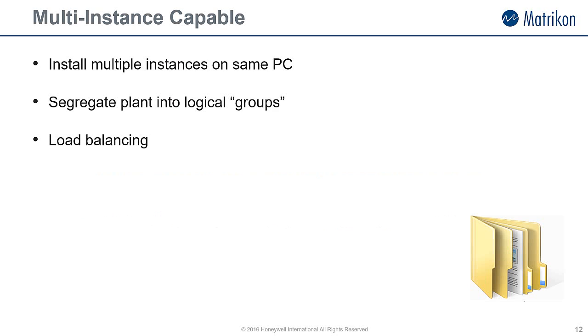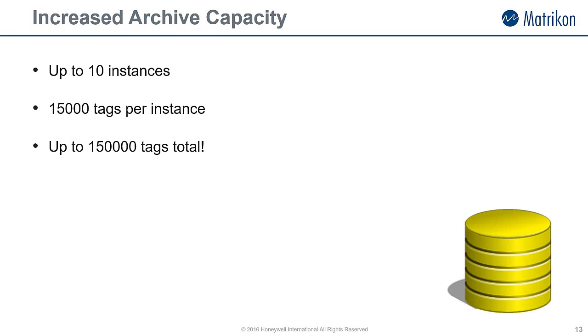First up, Desktop Historian is now a multi-instance capable product. This means we can install multiple instances of Desktop Historian on the one computer. You could use this functionality to segregate your plant into local areas, or maybe for load balancing. This also means a huge increase in the possible archived tag count. Previously, Desktop Historian was good to about 15,000 tags per install. In version 5.1, you can configure up to 10 instances with 15,000 tags per instance, which gives us a possible 150,000 total tag count.